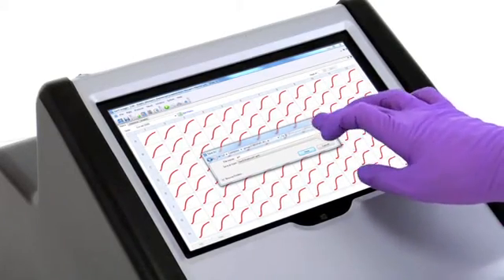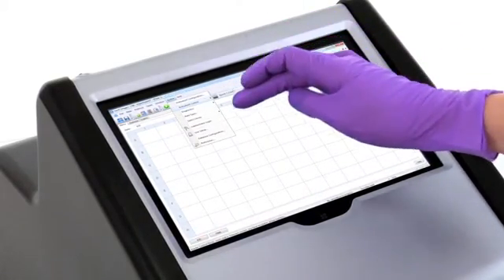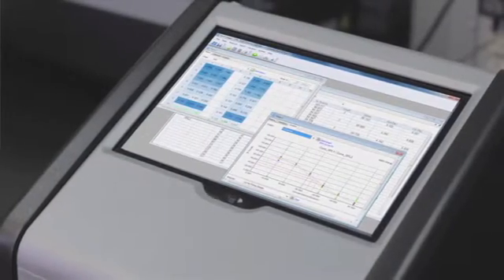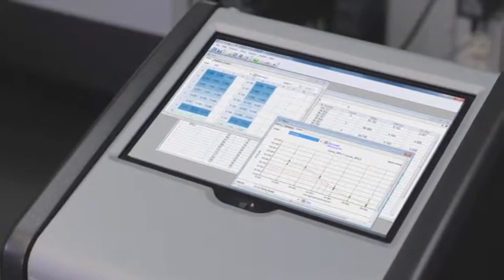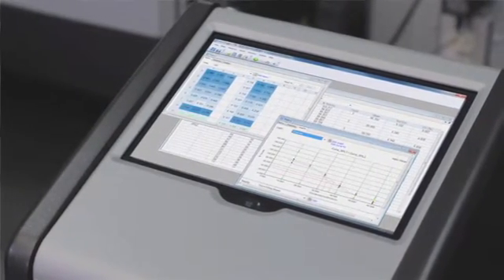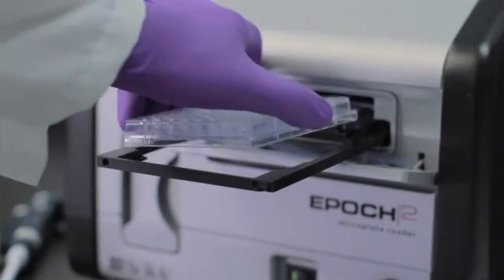The large color touchscreen available with EPOCH2 offers easy access to the intuitive, full-function Gen5 TS software for complete reader control and data analysis. Endpoint, kinetic, spectral scanning and well area scanning are all easily programmed in Gen5, while the powerful data analysis options include multiple curve fits from linear to 5-parameter, control validations and cutoff calculations.